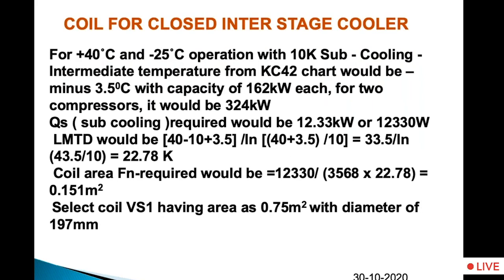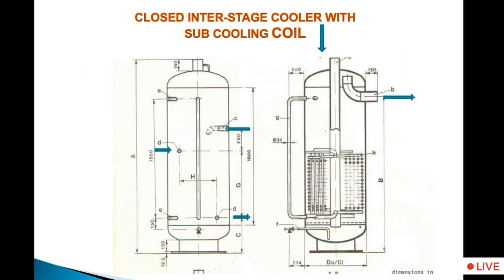But these are the calculations for the closed interstage cooler, and this is the construction. If you see inside the cooler, there is a coil. The gas comes down, and the gas is outside the coil. Inside the coil there is liquid ammonia, and the liquid ammonia cools down and reduces the superheat of the gas, and with less superheat the gas is then sucked by the high stage of the compressor. So this is the closed interstage cooler with subcooling coil, and I would recommend using this as much as possible.